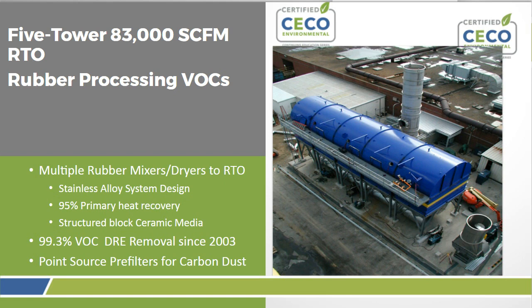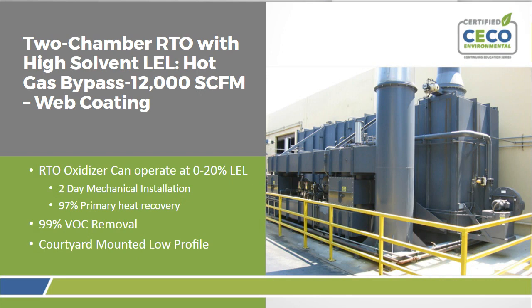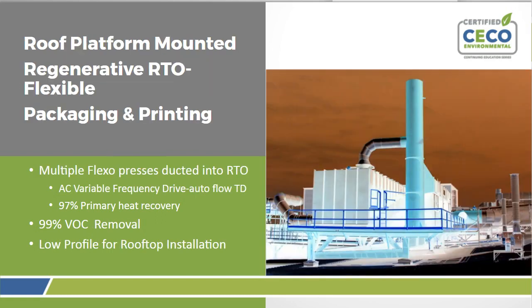Here's a typical low profile unit, again outside ground mount. This is on a web coating type application, high solvent, hot gas bypass, because they can occasionally get up to 20% LEL. And again, just low profile, so you want everything accessible pretty much from grade. Here we'll try to wake you up a little bit with Halloween. This is not a haunted RTO. We just had some special effects with a nighttime shot of a roof-mounted unit at a Flexo printing and packaging plant. And again, this has multiple processes going into one central RTO.